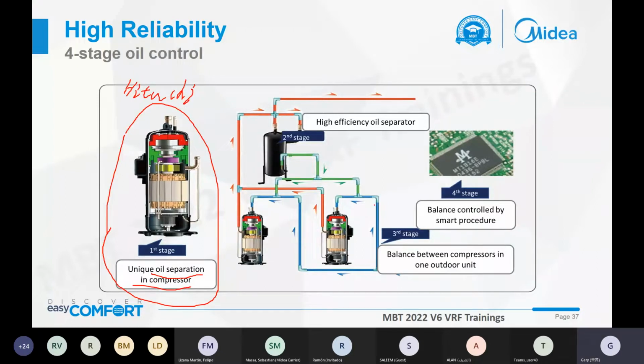And the second stage uses the high efficiency oil separator. Here is the separator. And the third stage is the balance between the compressors in one outdoor unit. These 2 compressors can balance the oil. And the fourth stage is we have smart logic built in the intelligent chip. This is the built-in logic. So it totally has the 4 stage oil control to make our compressor and the outdoor unit run more reliably.